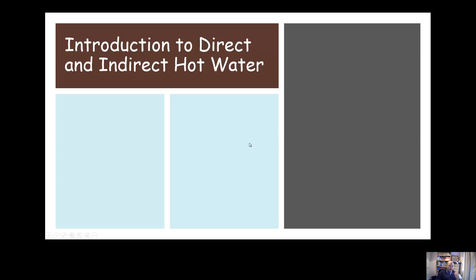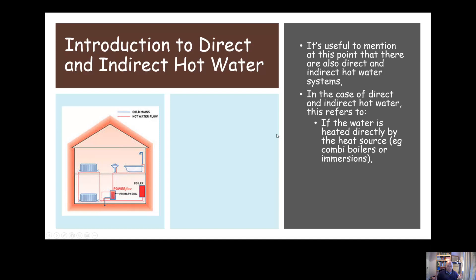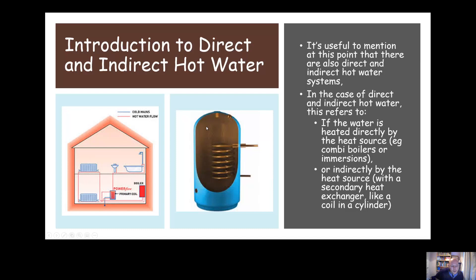It's a good time to introduce direct and indirect hot water, because they are slightly different. For hot water systems, direct and indirect refers to how the water is heated. In a direct hot water system, the water is heated directly by the heat source — for example, a combi boiler heats the water and it comes out of our taps, or an immersion heater sitting in the cylinder directly heats the water which then comes out of our taps.